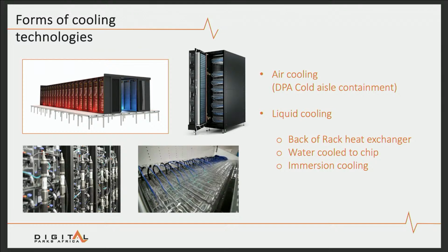not efficient anymore. So what's come along is a number of forms of liquid cooling and a couple of different implementations that we have seen, and we are starting to see more and more of them. The heat exchangers that are mounted at the back of the rack, fairly easy, small retrofit that is bringing the source of the cooling closer to the actual equipment. But even that has some limitations and some cost considerations.